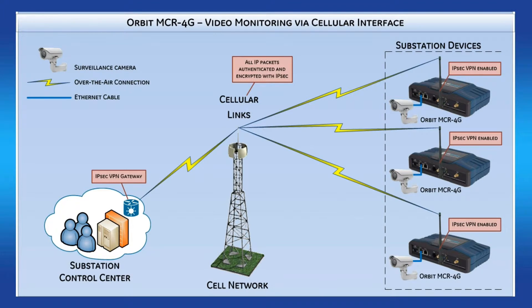The Orbit can also protect your data with extensive security protocols by the use of an IPSec VPN connection. With this feature configured, all data will be authenticated and encrypted between the remote private network and the substation control center. This is accomplished using the IPSec protocols of encapsulating security payload or authentication header. Further security can be applied with RADIUS standards, particularly when Wi-Fi clients or Orbit MCR900 units are included. This is known as device authentication, where the client must prove its identity using certificates applied by system administrators.